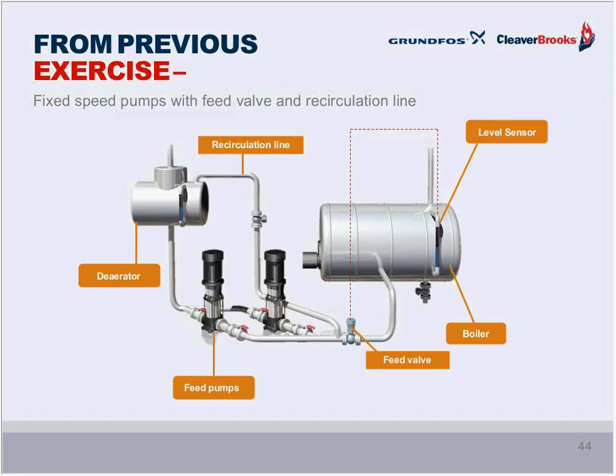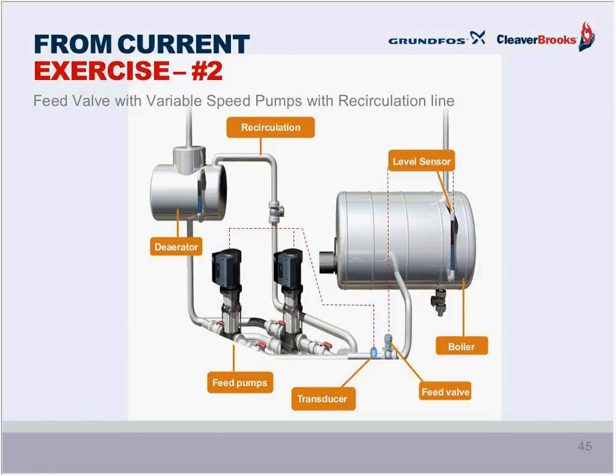So there's continuous flow even when that feed valve's completely open and the boiler water level needs to rise. That was what we did last time, and we're going to select another pump this time, and then we'll compare results in the two so you can see some advantages to each method. Okay, so what we're going to do now is select a pump using this variable speed pump and motor instead of fixed speed. It's also going to be continuous duty, so there will be a bypass line just like last time, and there's also a feed valve just like last time.